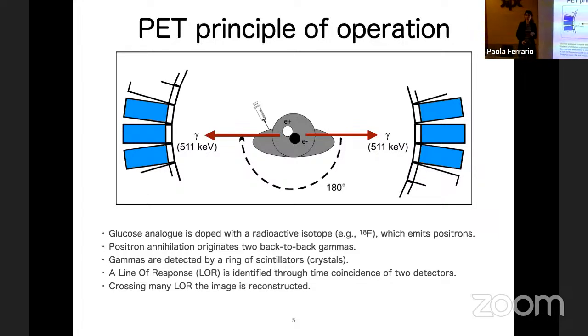The only requirement of this isotope is that it needs to emit positrons, so it needs to decay beta plus. So the positron at some point annihilates with one of the electrons of the body of the patient. And from this annihilation, 2 high energy photons of around 511 keV are emitted in opposite directions.